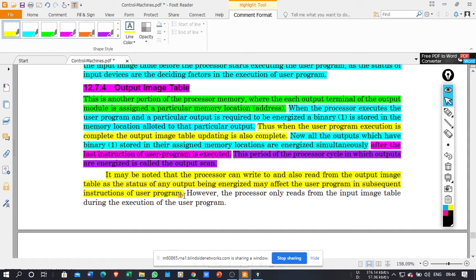Sometimes, if I'm going to energize a particular output, some other output may be dependent on it. So my second output may depend on the first output, in which case I need to read from the output image table to know whether the first output is on or off.